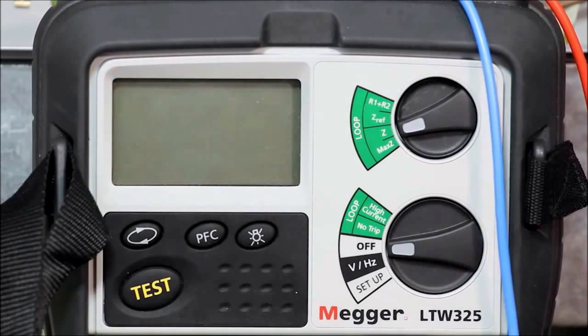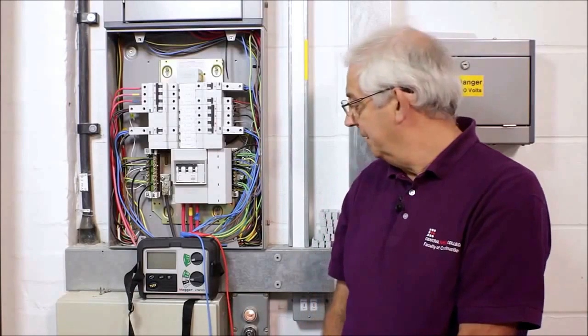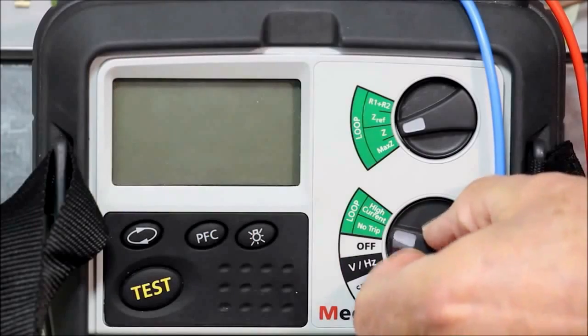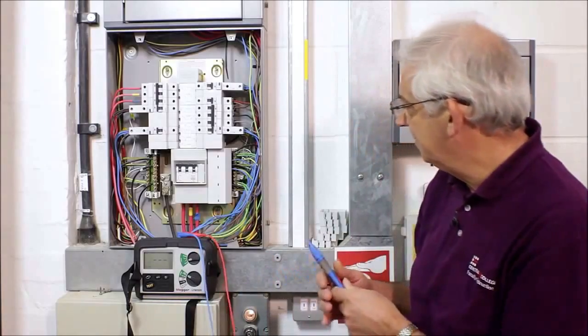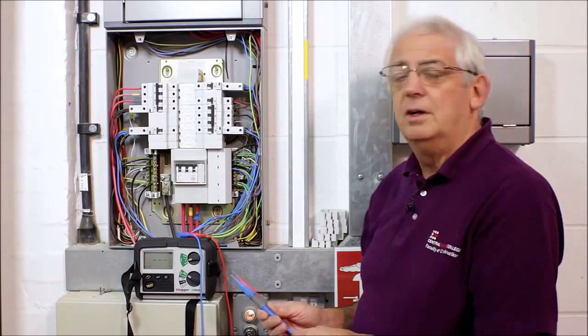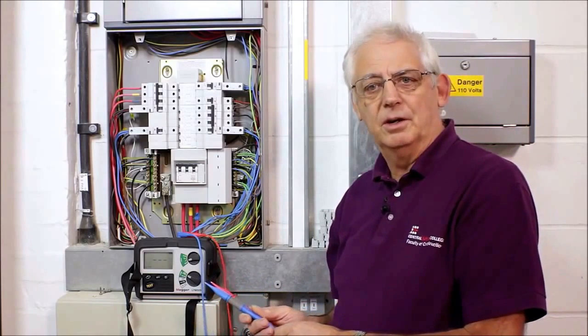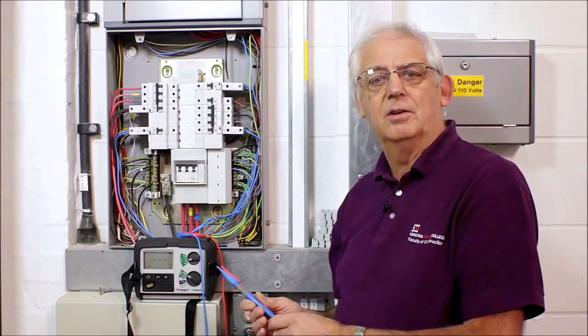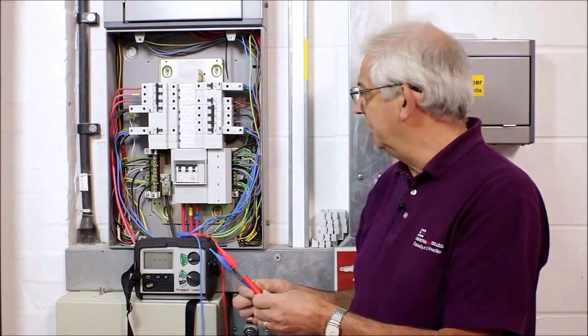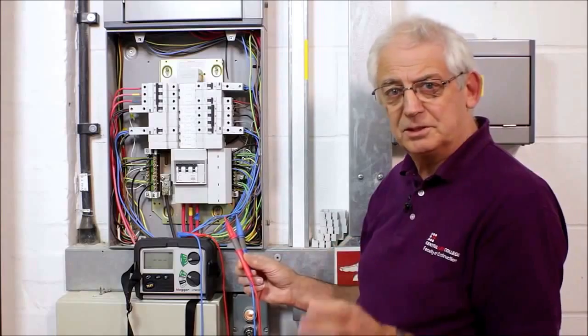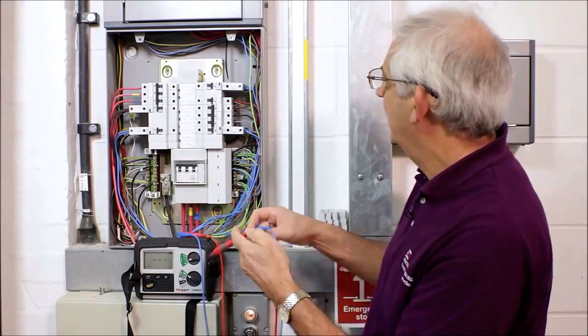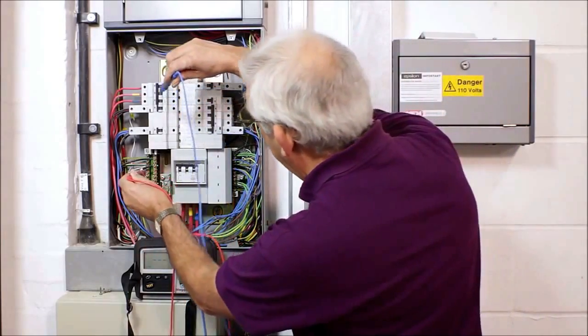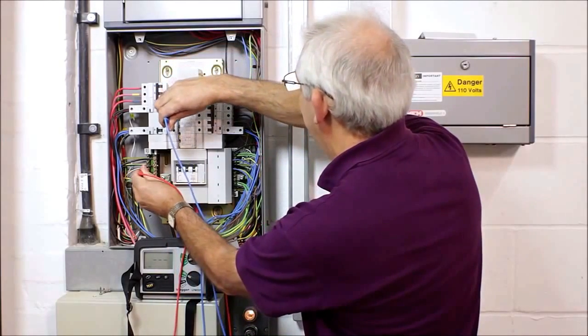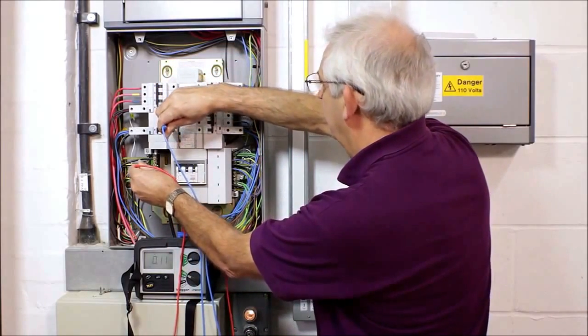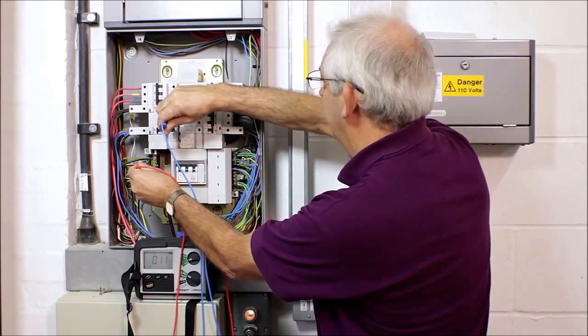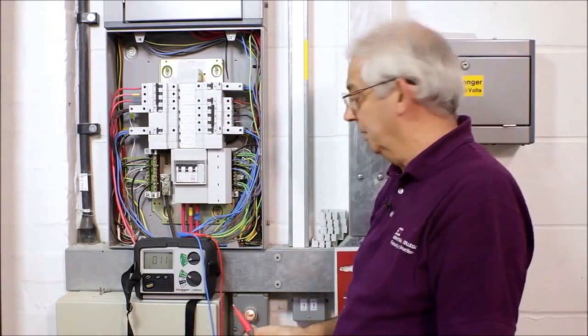Our earth loop instruments normally do the same job. So for that, I'll turn it on to high current, and then I test between, first of all, I need to know prospective earth fault current, which is the maximum current that could flow between any line conductor and earth. So with 2 leads, remember this is a live test, so you must take great care at all times. I go from my earthing terminal to our L1. Earthing terminal to L1.